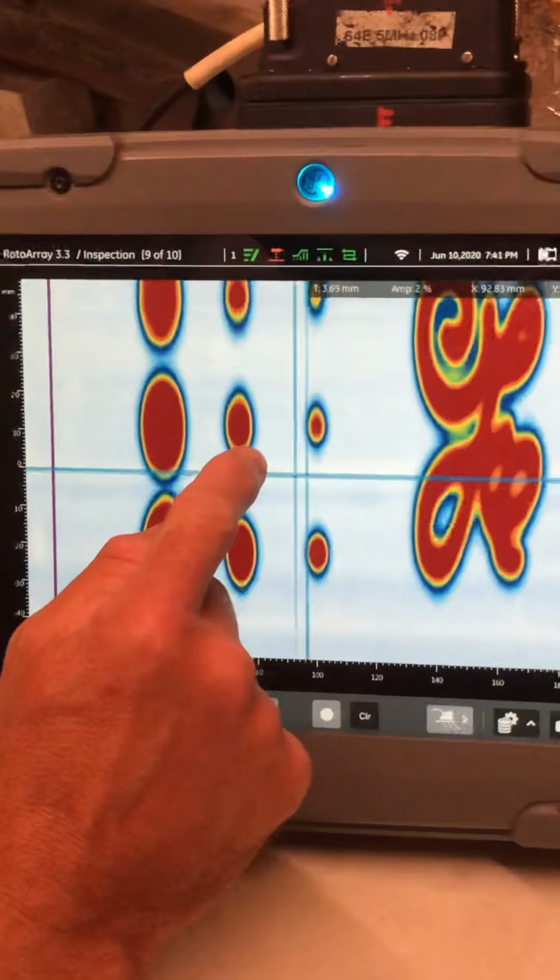Right, what we have here today is this 64 element linear array that's hiding on the axle inside this tire filled with a liquid. And we've got it plugged into our set. And what we're going to do, we're going to drive it over this bit of perspex that's got different depth flat bottom holes and a bit of a logo cut into it, and see what happens.